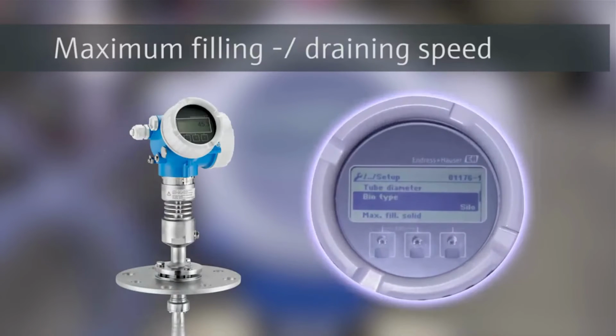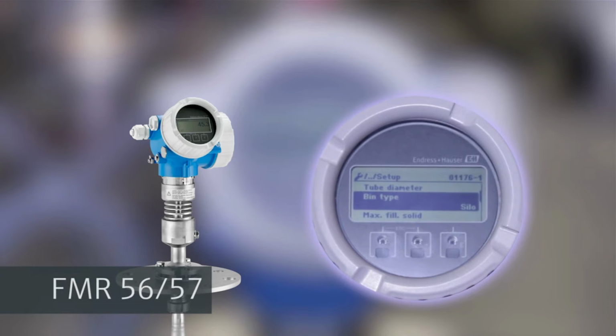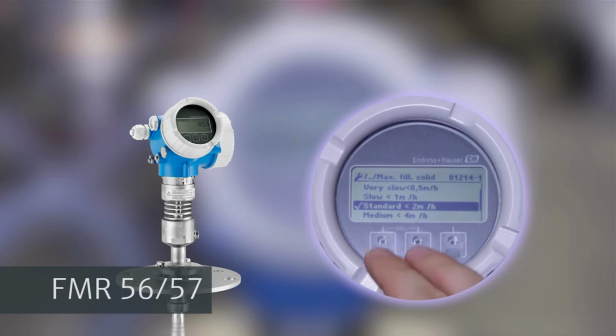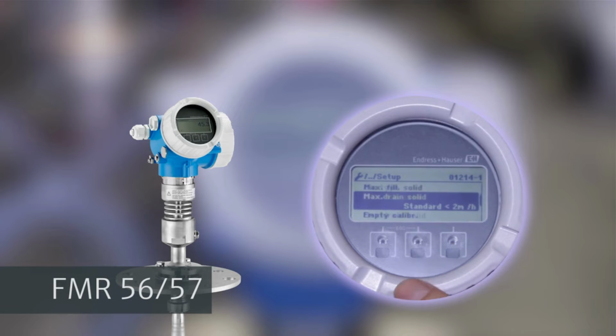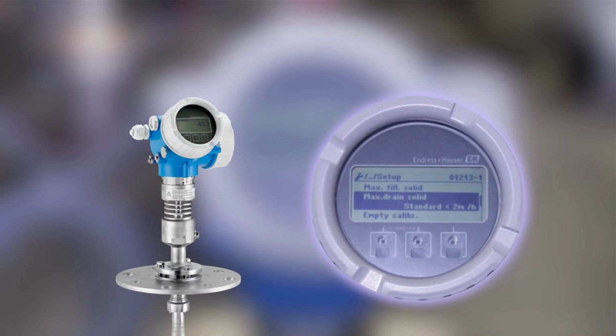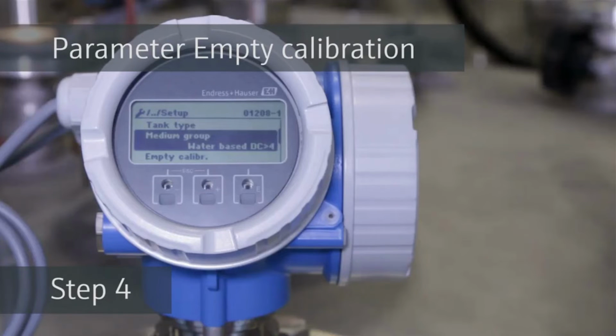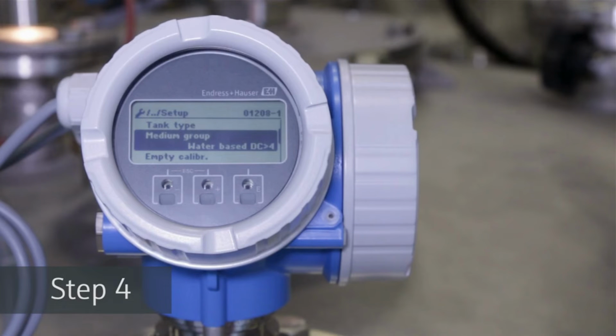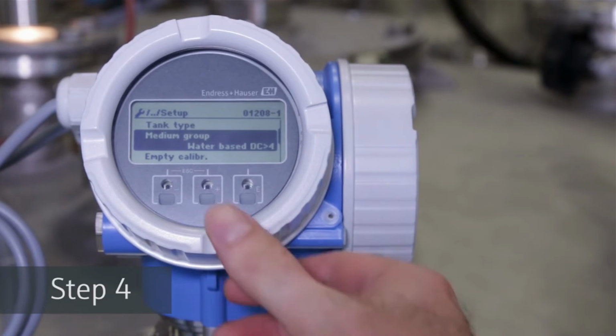In level measurement of bulk solids with Micropilot FMR56 and 57, determine the maximum filling speed and then the maximum draining speed of the silo or process in this menu step. In the next two menu items, please enter the measuring range. Start as displayed by the instrument by determining the empty calibration.